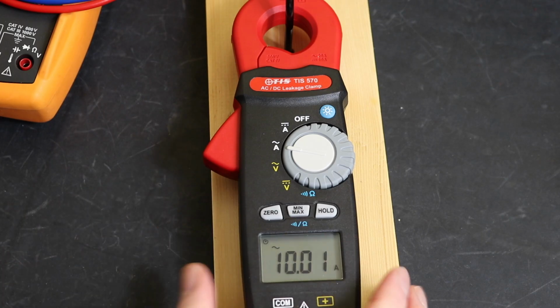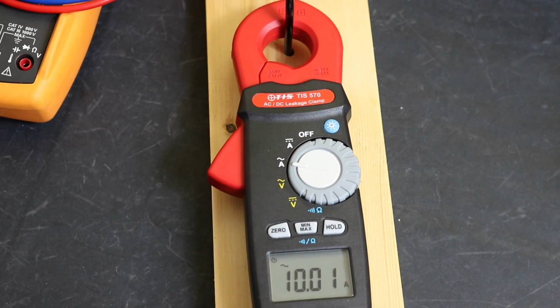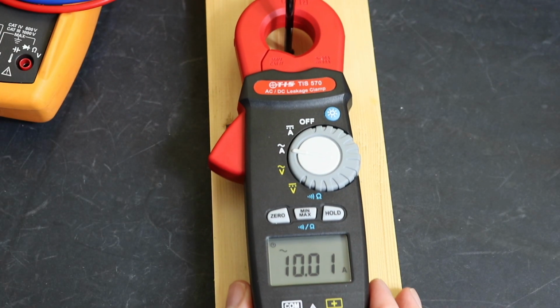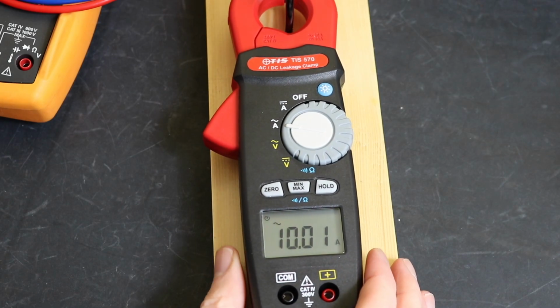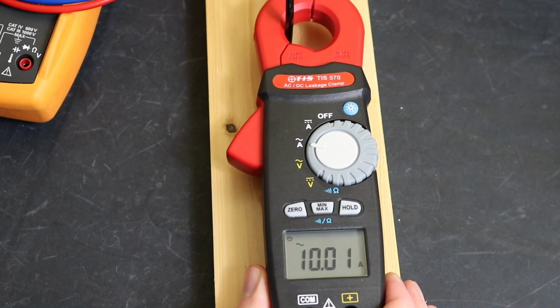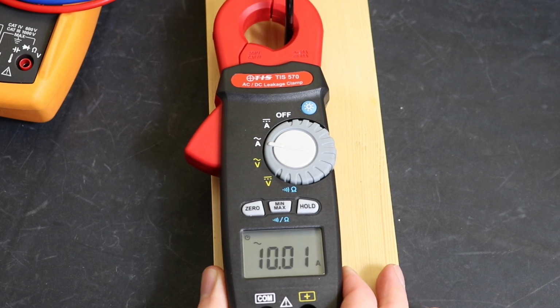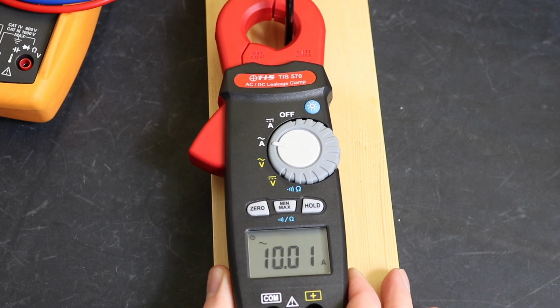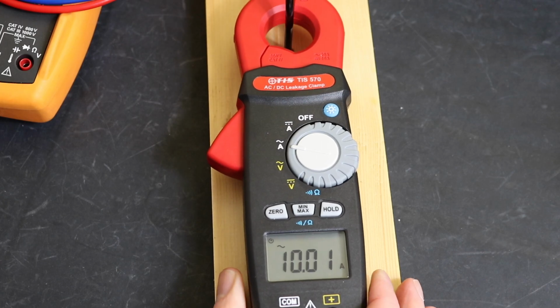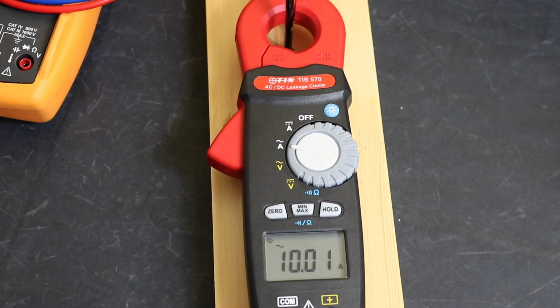I know this is quite a small head, but we'll just move it around and just see what variation we get. 10.01 top, 10.01 bottom, 10.01, so you can see it's a very, very stable clamp meter in that respect. No problems whatsoever there. We'll just flip this to 60 Hertz. So we can see there 10.02, so we can see it's shifted 0.01 amps, and even then it's floating around, so that's perfectly acceptable. Now we'll just switch off and convert this to DC.